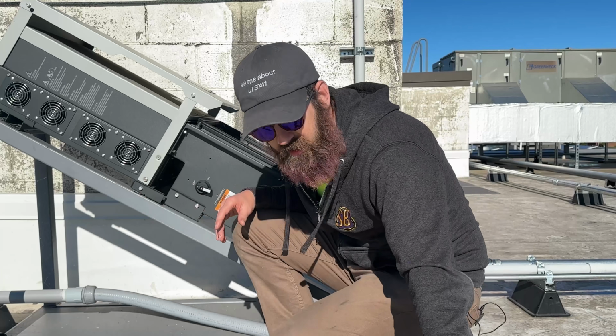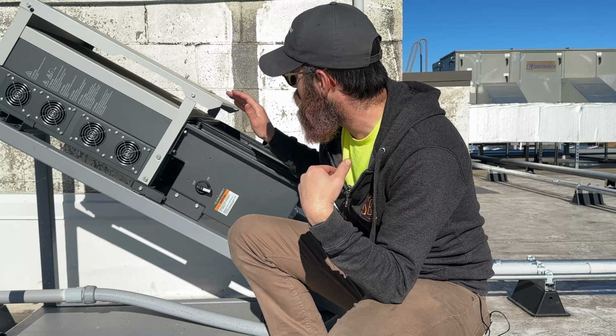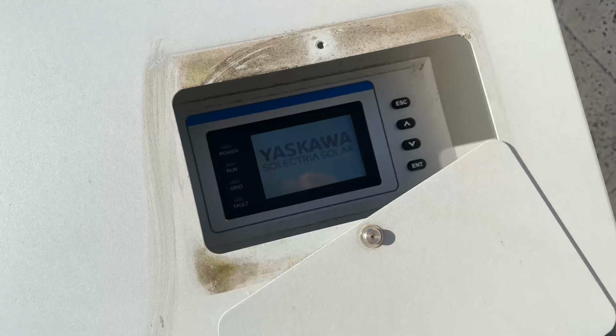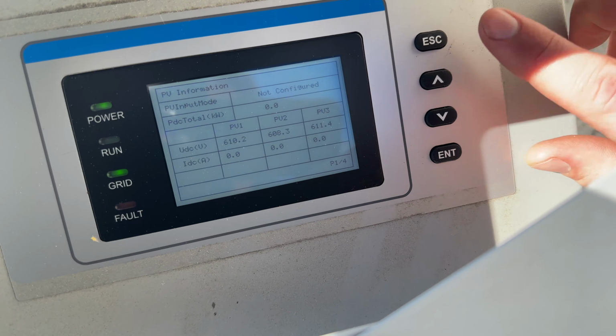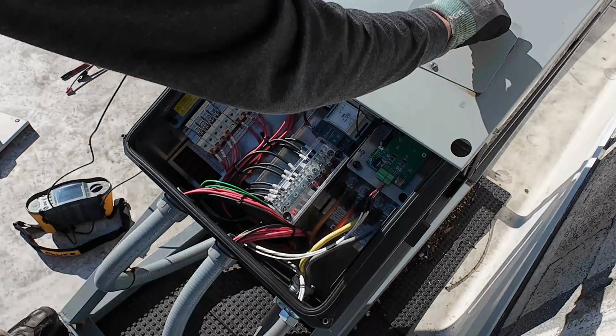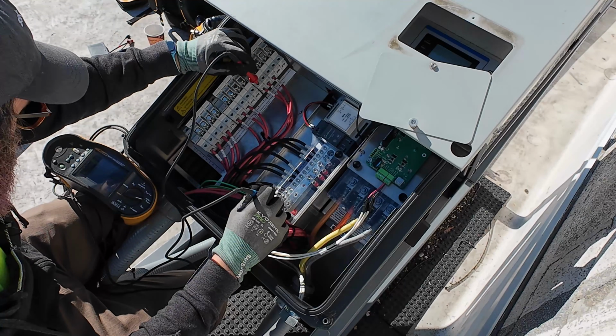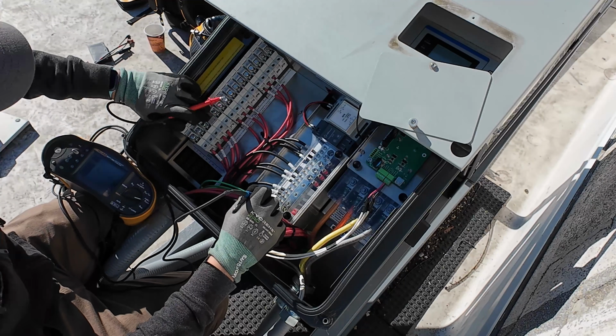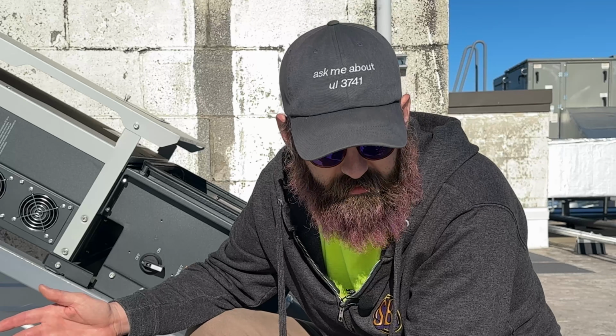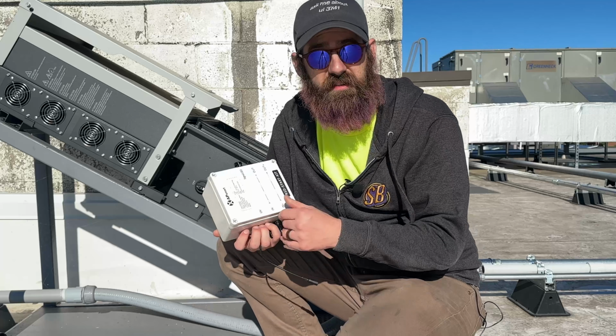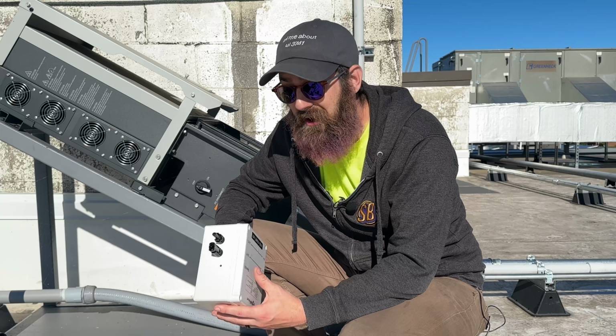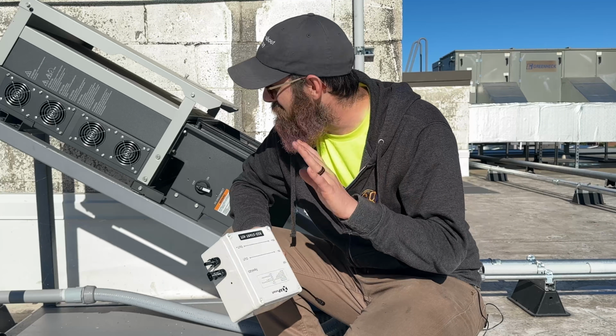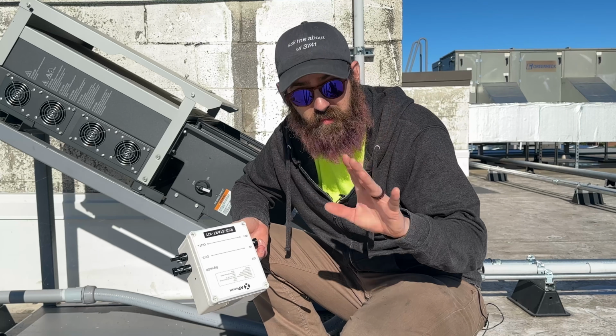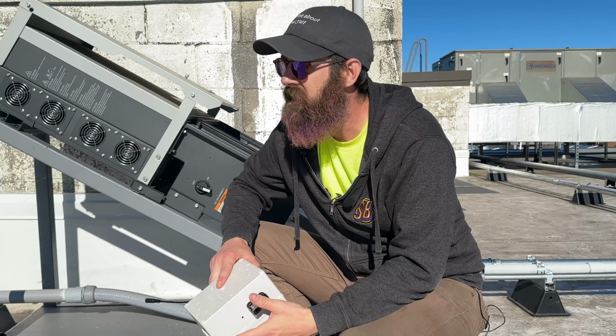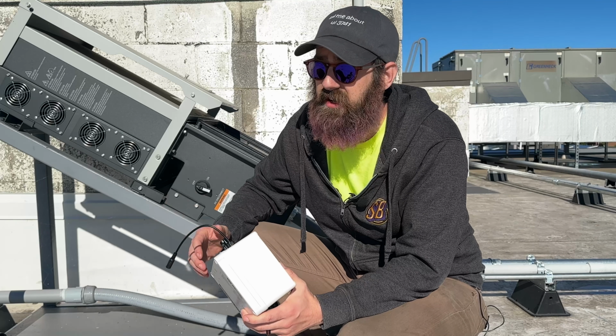In practicality, what I've done most of the time when commissioning an inverter like this is turn the entire inverter on, and before it hits its production cycle, go through each fuse individually, close each fuse, and voltage test just on those strings, which works fine. It's annoying, but it works totally fine. You could theoretically curve trace the same way, but I don't know how much that might mess with the inverter. I'm not as familiar with the super technical bits on that front, but theoretically it's possible.